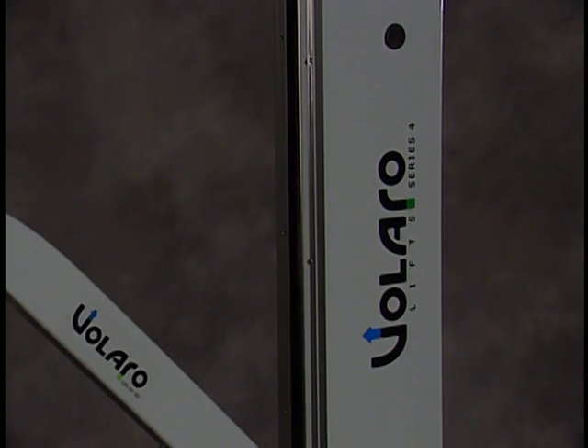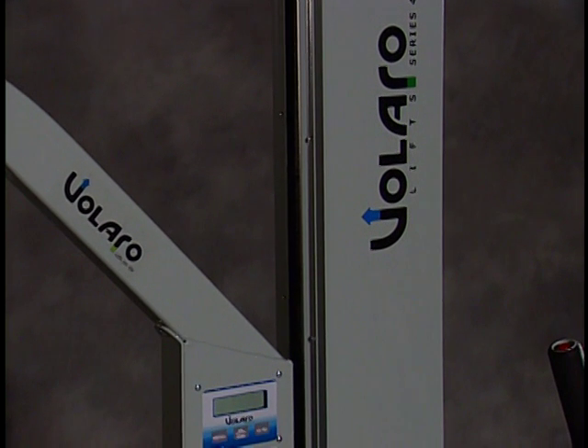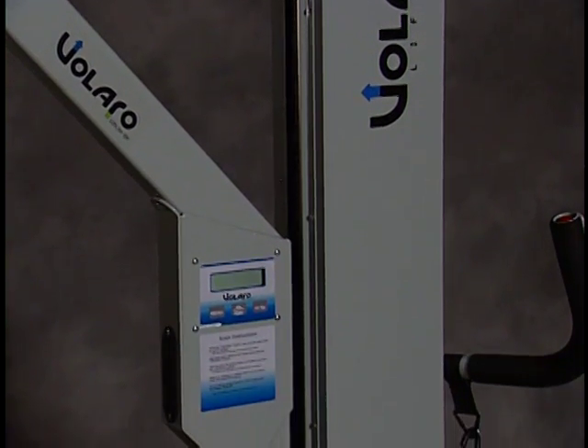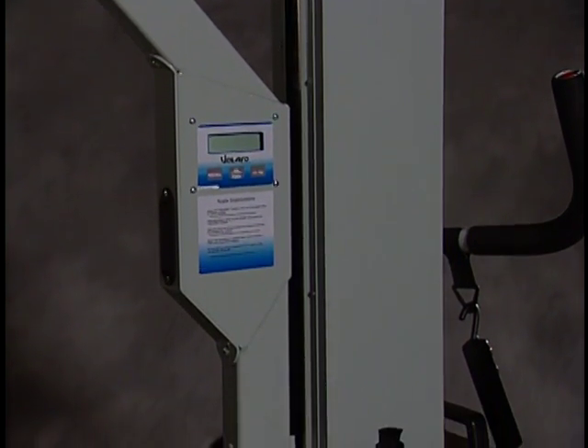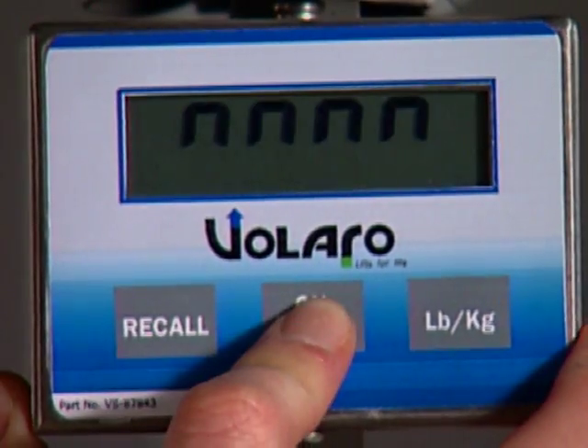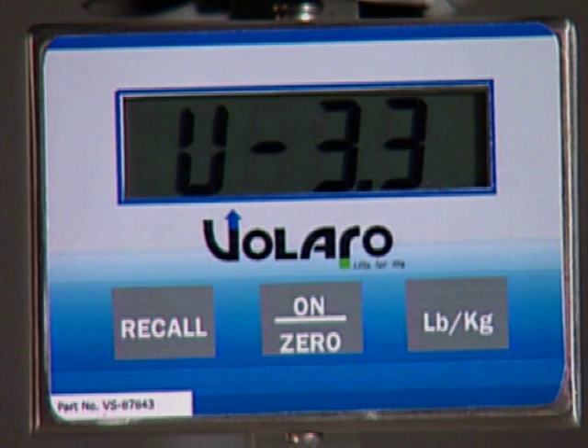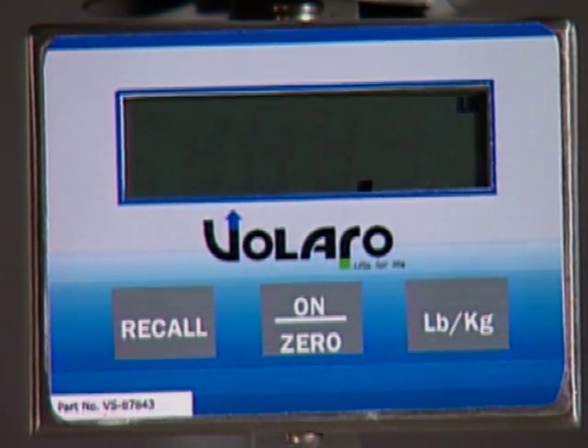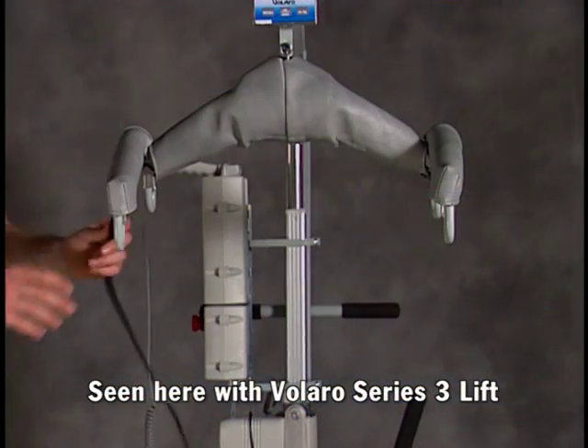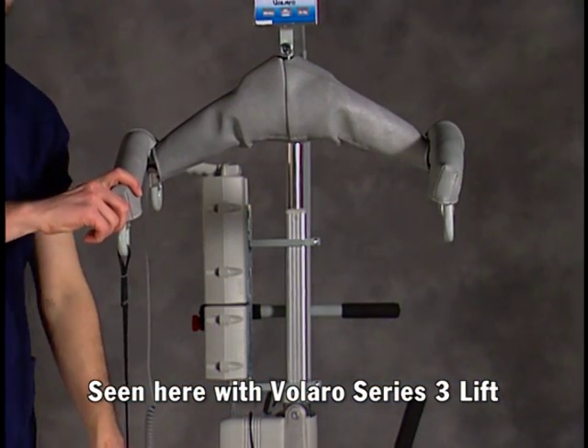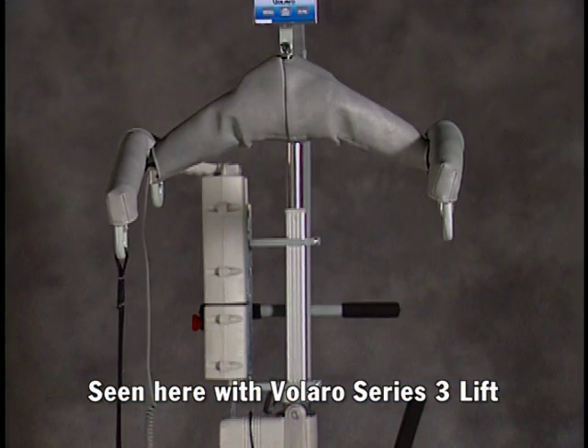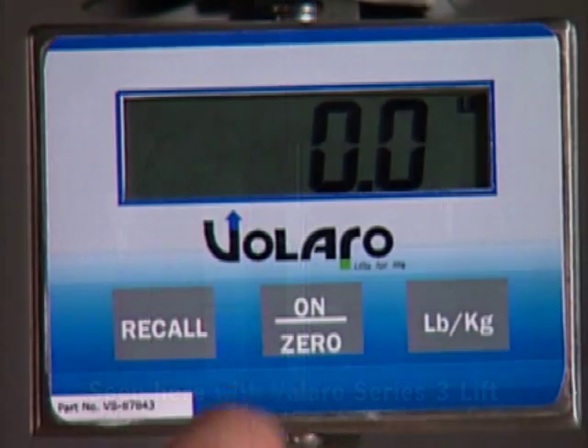Locate the lifting arm or beam in the middle of its travel range. Note, make sure that the remote hand control is not hanging from the lift beam. Turn on the scale by pressing and releasing the On Zero button. Wait until the scale runs through its startup process. Suspend from the hanger bar the straps from your calibration package that will hold the calibration test weight, making sure they are not touching the ground.